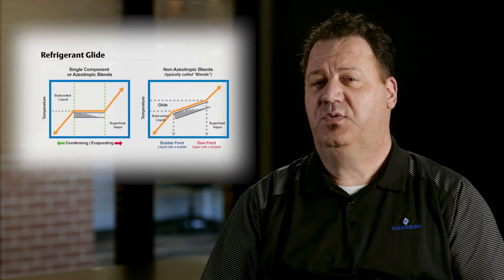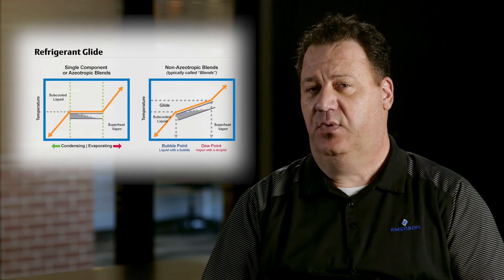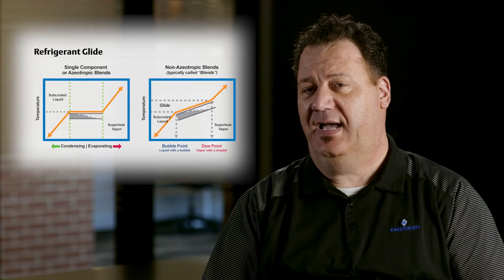When we talk about Glide, what we're really talking about is the different temperatures in the boiling point. If you have four components, one component might start out at a certain temperature, and the fourth component will end at a different boiling point. The difference between the starting point and the ending point is our Glide.